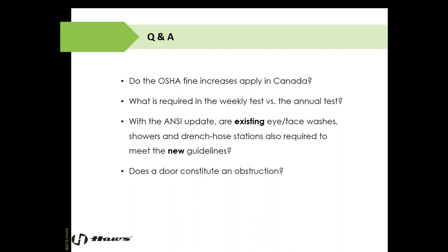Most facilities do not have ADA accessible first aid emergency showers and eyewashes. The reason is, in the ADA standard, if you have given somebody with disabilities access to that part of your facility, then it has to meet the ADA requirements, which means you need a lower eye face wash to accommodate somebody in a wheelchair, a longer pull rod so that they can reach it from their wheelchair, et cetera. Most manufacturing facilities that don't give access to these parts of their facilities don't have the requirement to provide ADA accessible emergency equipment. So yes, longer pull rod, yes, lower eye face wash, but no, most facilities don't have that type of equipment because they don't allow access for somebody who is handicapped.